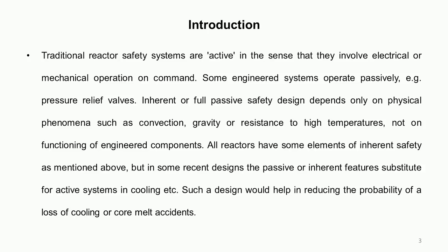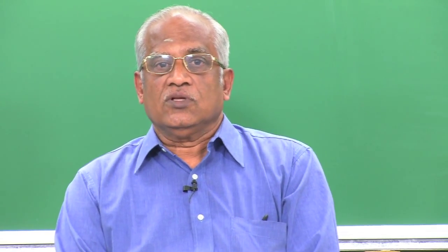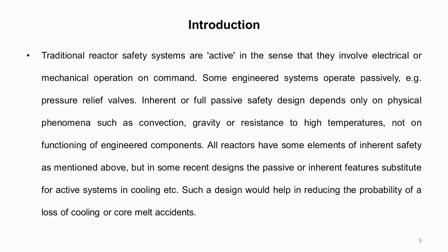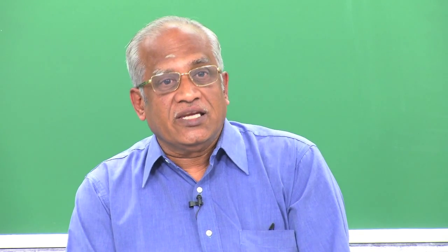Another approach: if you require a coolant for reactor cooling and you don't want to rely on a pump, you put your tank at a high level. In that case, if your primary pump fails, the pressure comes down and your non-return valve can open, and the water will come down from the tank just by means of gravity. So this is again a sort of passive, or also called inherent, safety feature of that design.